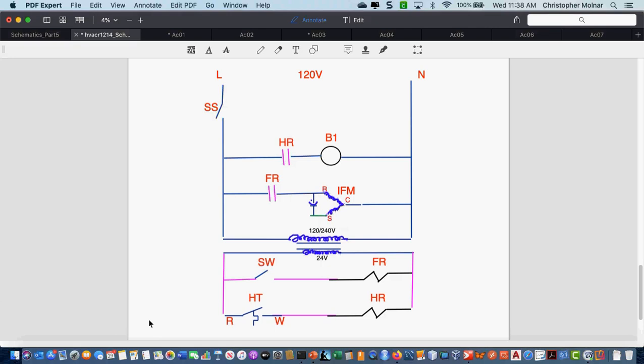The older burner motors, like the ones on furnaces and boilers that are 20, 30 years old, are all going to be capacitor start, induction run. But as we've gotten more efficient, we want that additional capacitor in there because it really helps with efficiency. So what I'm going to do is get rid of these two components there. I'm going to make room for my motor here. Okay, and I'm basically going to use the same motor that I just drew down there, and put it up there, we hope.